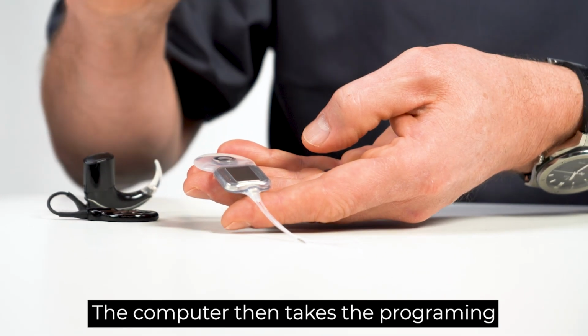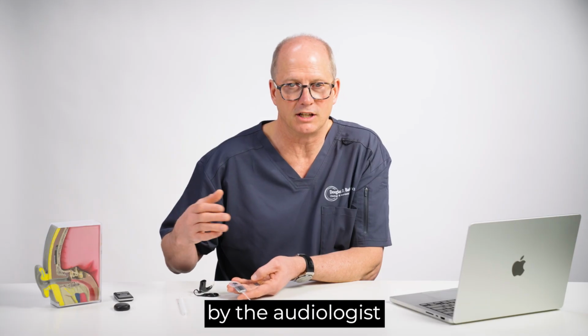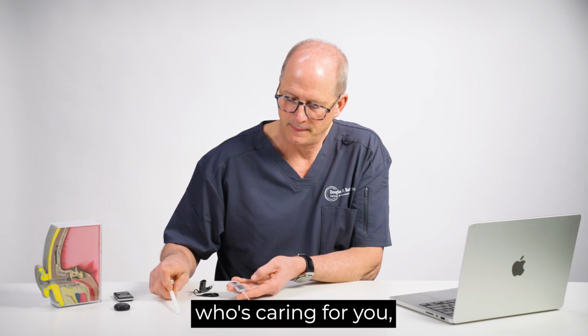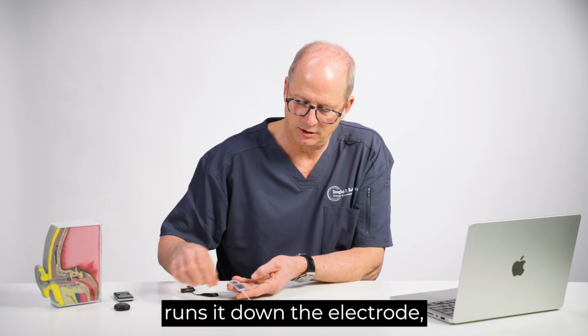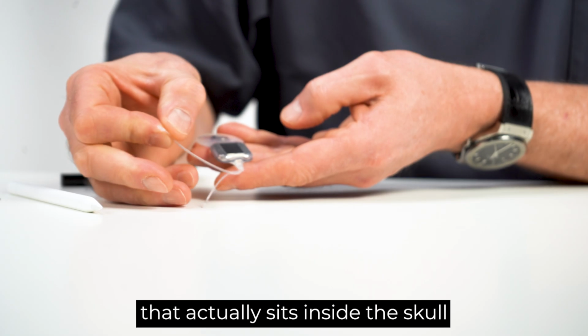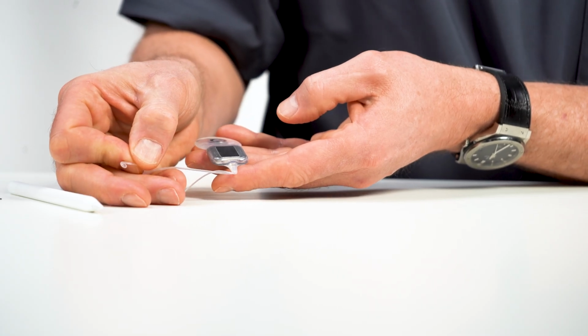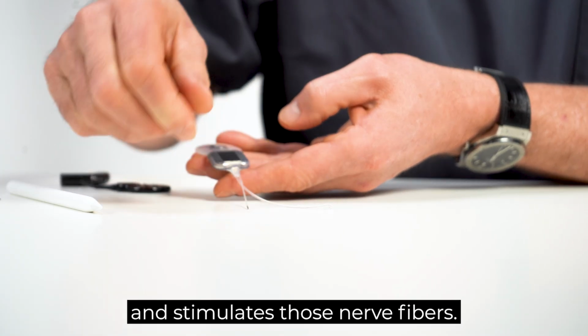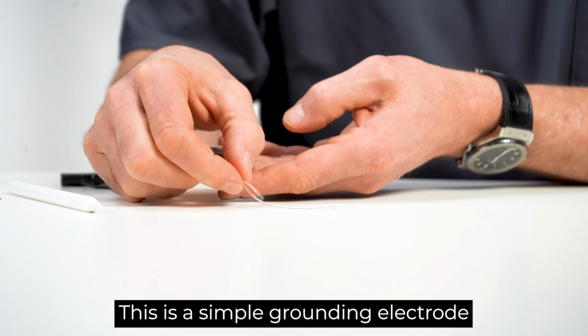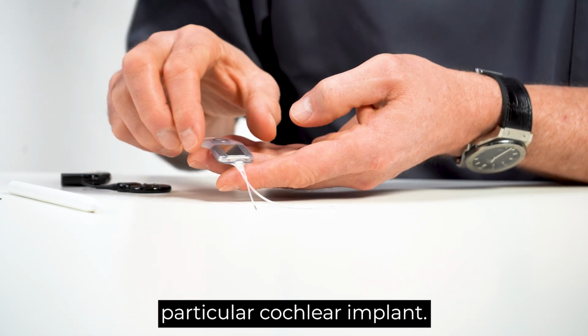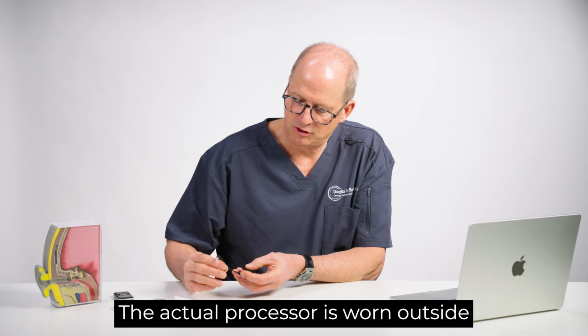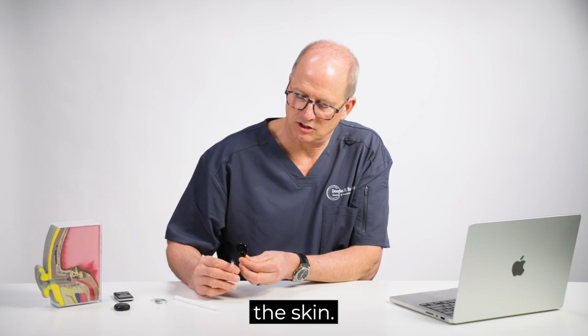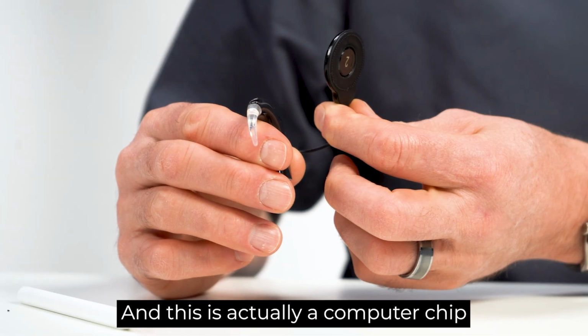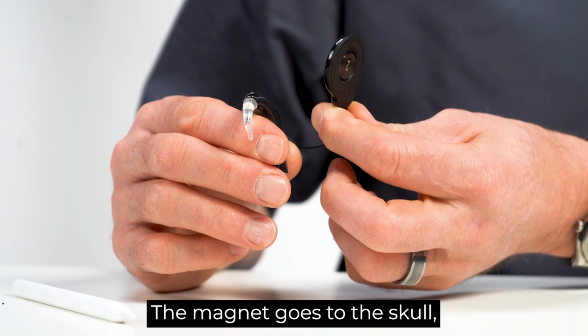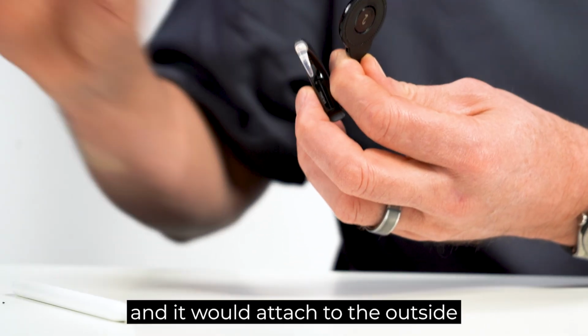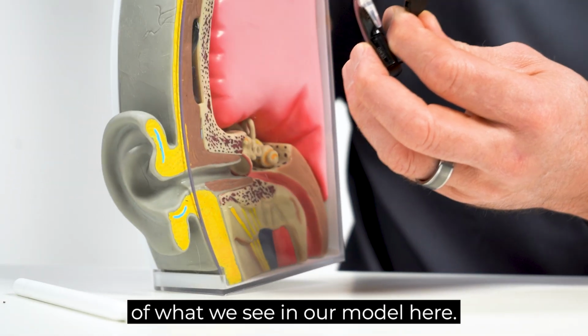The computer then takes the programming that's typically done by the audiologist who's caring for you, runs it down the electrode, and this is the active electrode that actually sits inside the skull in the cochlea and stimulates those nerve fibers. This is a simple grounding electrode, which is a component of this particular cochlear implant. The actual processor is worn outside the skin, and this is actually a computer chip-driven component as well. The magnet goes to this skull, and it would attach to the outside of what we see on our model here.